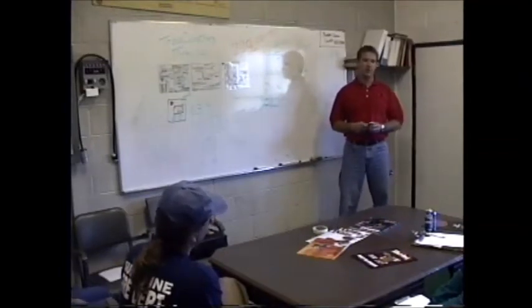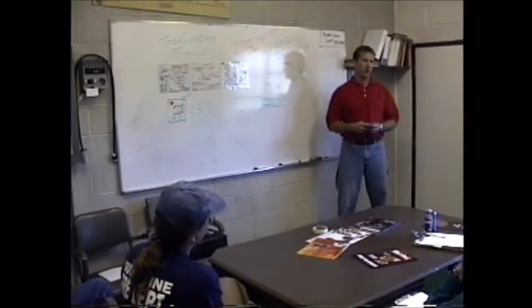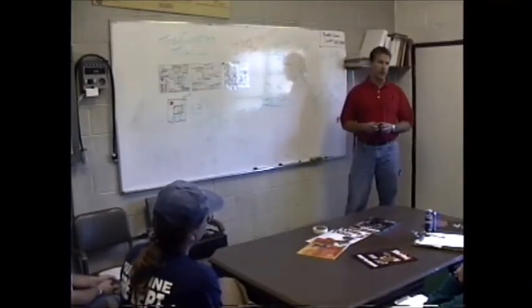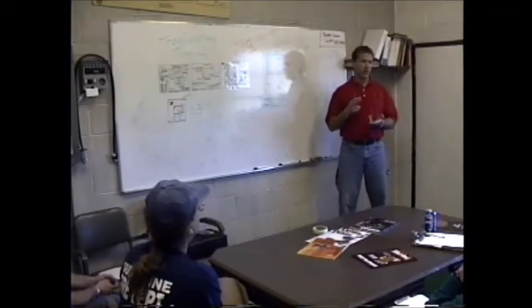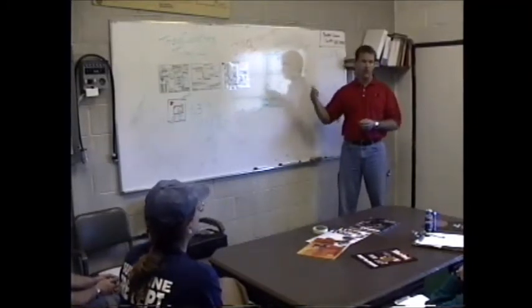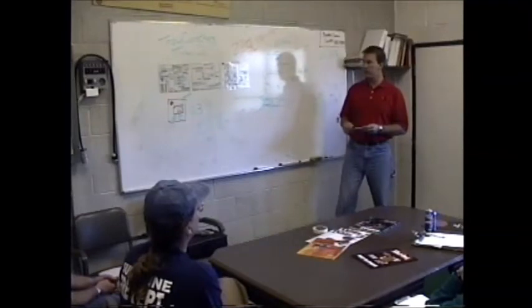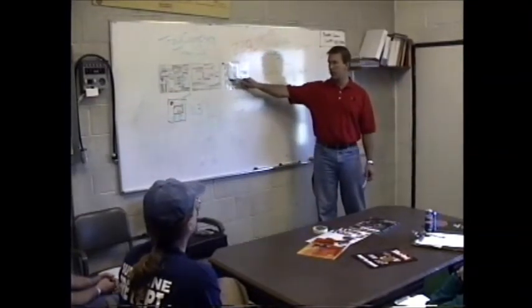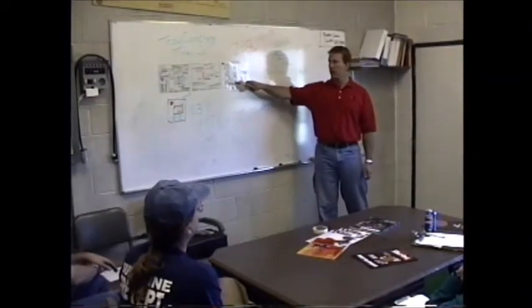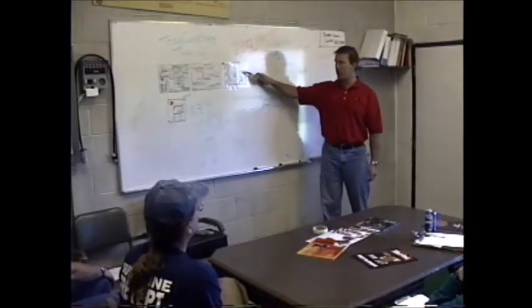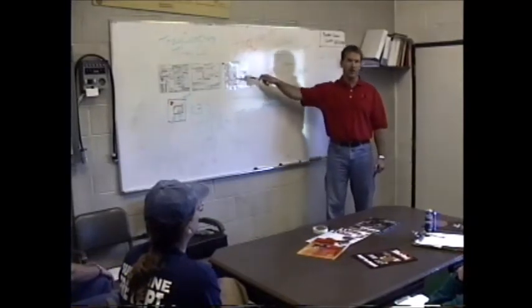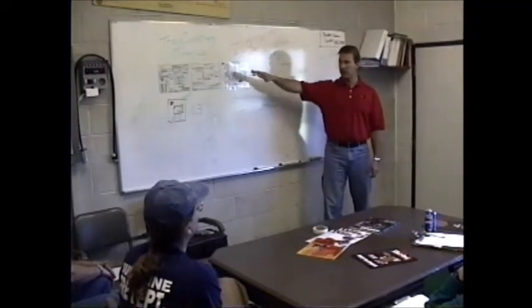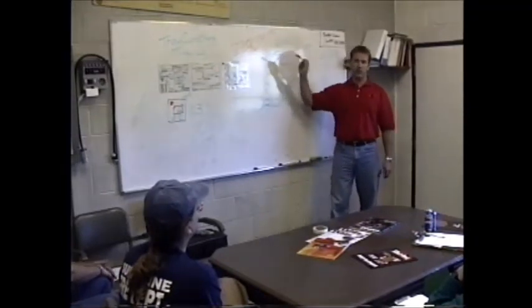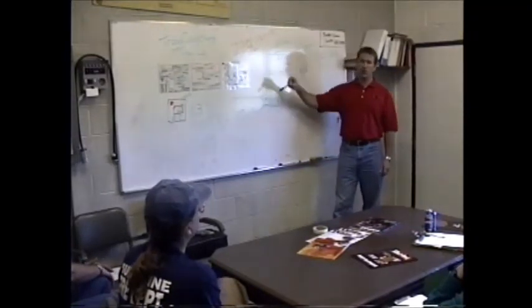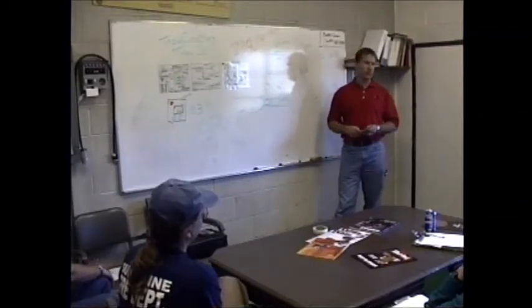And it's not much more expensive than a typical SAE type of car oil. It's just a little different weight and a little different makeup, so it's anti-foaming and some of those things, because when you're pumping it at such a high velocity, we're moving the entire quantity, these 14 quarts of oil that's in this tank, every minute through that compressor and back to that tank. So every 60 seconds, that entire quantity of oil has gone through the compressor and gone back to the reservoir. It's really moving the oil through the system in a hurry.